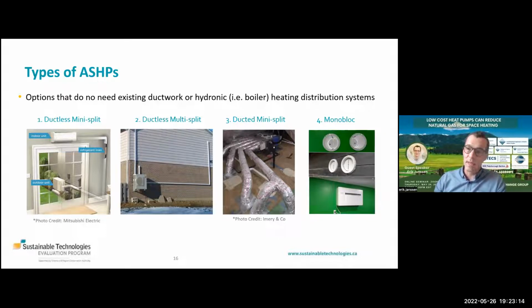For example, there are ductless mini splits, with a single outdoor condenser connected to a single indoor ductless fan coil. Scaling that up, there are ductless multi-splits, with one outdoor condenser connected to multiple ductless indoor fan coils. You can run the refrigerant lines on the exterior of the building—this picture is from a pilot of this technology we did back in 2018. This is especially beneficial for electrically heated homes that don't have any heat distribution system, like ductwork or hydronic piping for a boiler, so you can easily retrofit a heating distribution within a home using that approach.